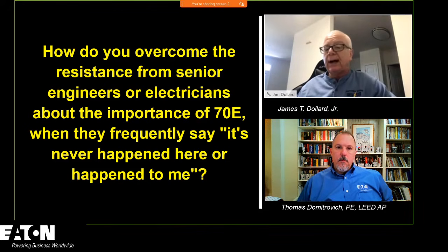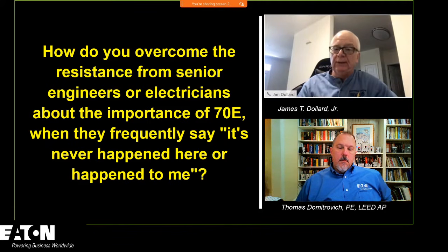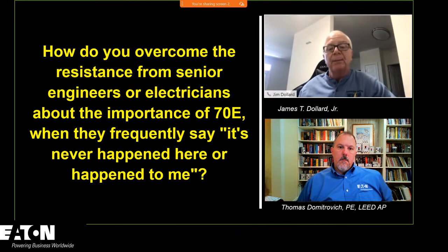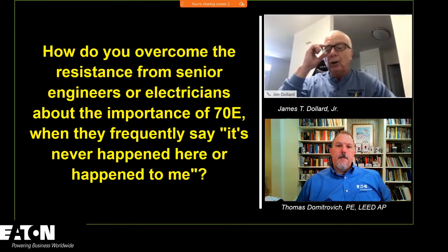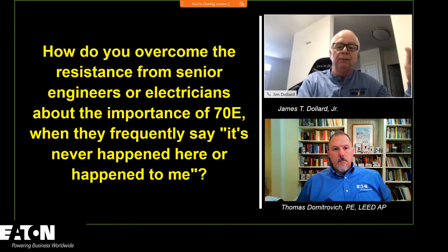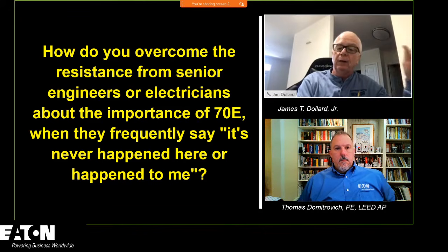I can tell you OSHA will not and cannot cite 70E. OSHA will use 70E, and they will use it in a very significant manner, to prove that, one, a hazard existed, and two, that there was an industry consensus standard well known that could have been used to abate that hazard, reduce the risk, or eliminate exposure. But if OSHA comes in, they're going to be citing their own requirements.